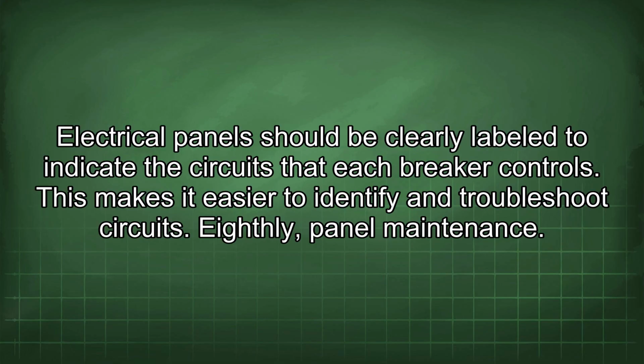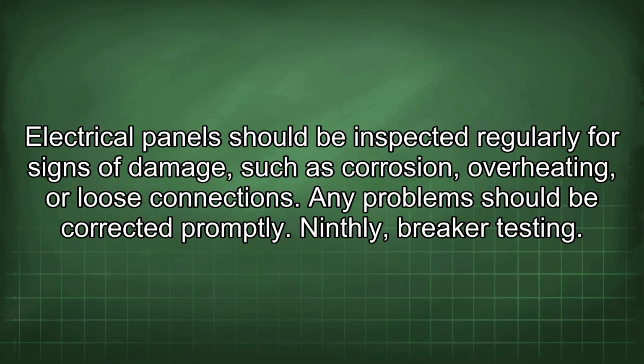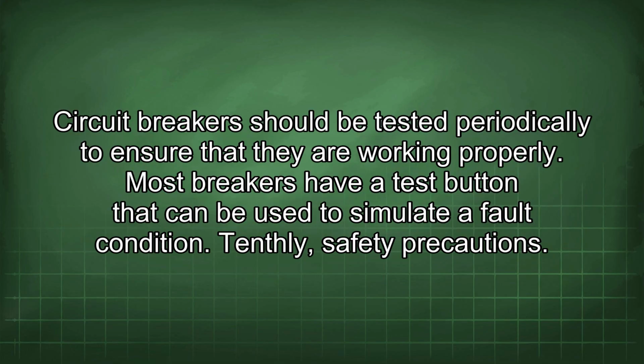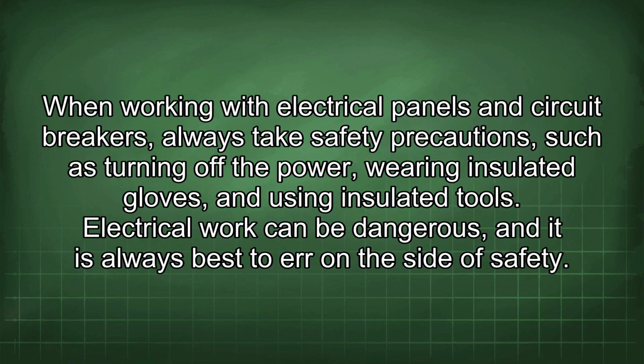Eighthly, panel maintenance. Electrical panels should be inspected regularly for signs of damage, such as corrosion, overheating, or loose connections. Any problems should be corrected promptly. Ninthly, breaker testing. Circuit breakers should be tested periodically to ensure that they are working properly. Most breakers have a test button that can be used to simulate a fault condition. Tenthly, safety precautions. When working with electrical panels and circuit breakers, always take safety precautions such as turning off the power, wearing insulated gloves, and using insulated tools. Electrical work can be dangerous, and it is always best to err on the side of safety.